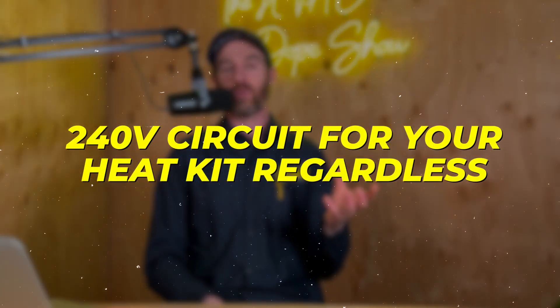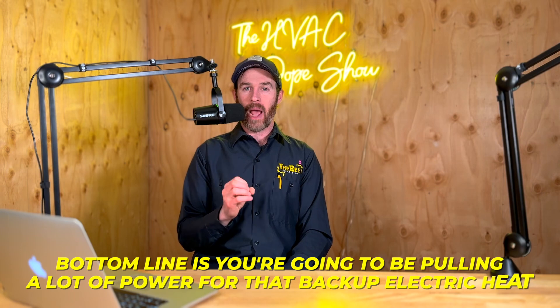Now that's not true for all heat pumps — we talk about a lot of cold climate heat pumps on this channel. The reason you have a 240 volt air handler, or why they've all been that way, is because you're going to need to run a 240 volt circuit for your heat kit regardless, since your backup electric heat kit is typically going to be a pretty large breaker. It could be 60 amps, could be 100 amps. If you have a really big house, it could be 125 or 150 amps just for the heat kit — normally it would be a two-pole kit at that point. Bottom line is you're going to be pulling a lot of power for that backup electric heat, because it's just big electric coils that you're heating with.